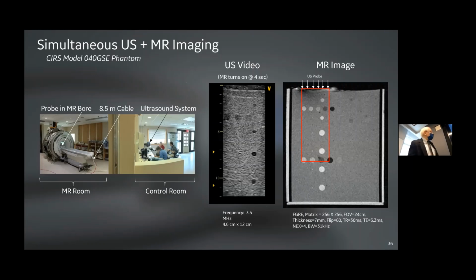Can you make all this stuff work together? Here's an example, just testing it out on some phantoms, but you can see this is in fact a single frame picture. So on one side, you can look into the magnet room and see the probe with its unusually long cable. We had to do some fun engineering with that. That then goes through a panel in this wall over to the ultrasound imaging machine, which is in the background there. And now, with a little bit of luck, if this video plays appropriately, you may be able to see on the very bottom that 4 seconds into it, it will go from being very clean on the bottom to having a bunch of streaks that go vertically.